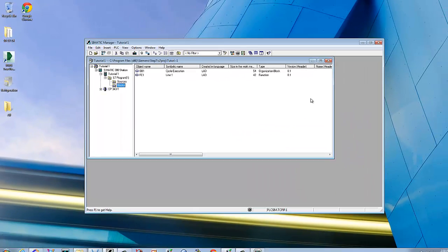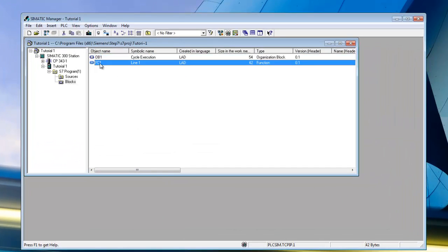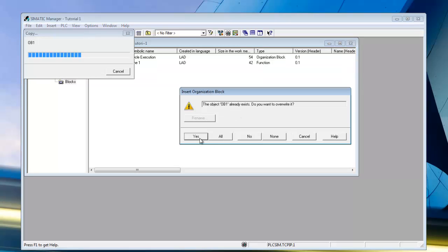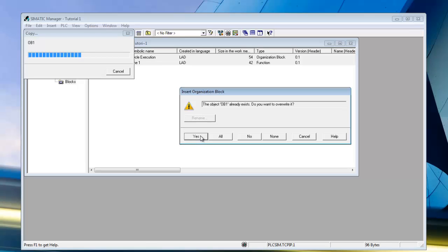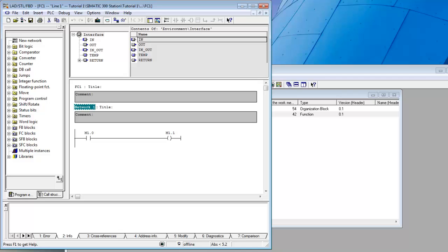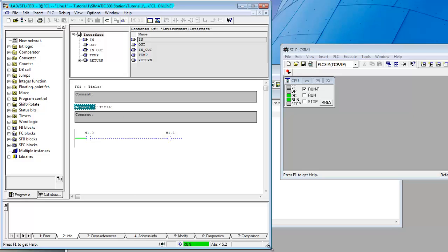We'll go ahead and download this to our simulator using the download button. We'll override it and everything has been downloaded to the processor. We can open up the function block to modify it and see it actually running. In the simulator, we'll go from Stop to Run Program and now it's running. To view it working, go up to the eyeglasses icon and select it — now it shows you're online with the simulator.